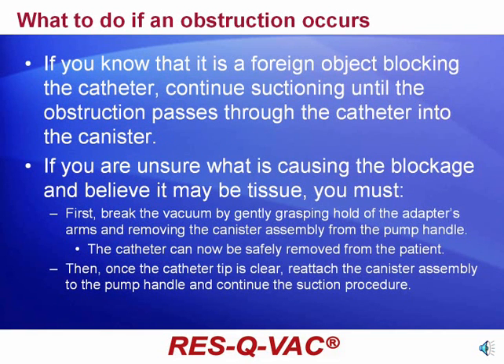If during suctioning you feel that the handle becomes difficult to squeeze, an obstruction may have occurred. If you know that it is a foreign object blocking the catheter, continue suctioning until the obstruction passes through the catheter into the canister. If you are unaware what is causing the blockage and believe it may be tissue, you must first break the vacuum by gently grasping hold of the adapter's arms and removing the canister assembly from the pump handle. The catheter can now be safely removed from the patient. Then, once the catheter tip is clear, reattach the canister assembly to the pump handle and continue the suction procedure.